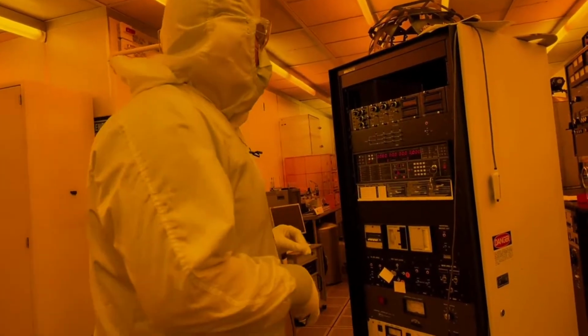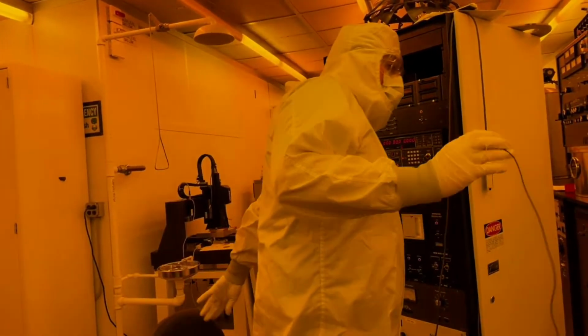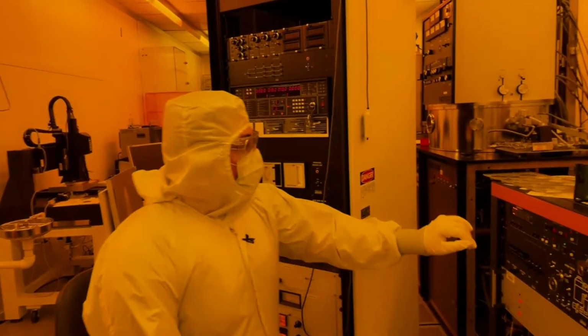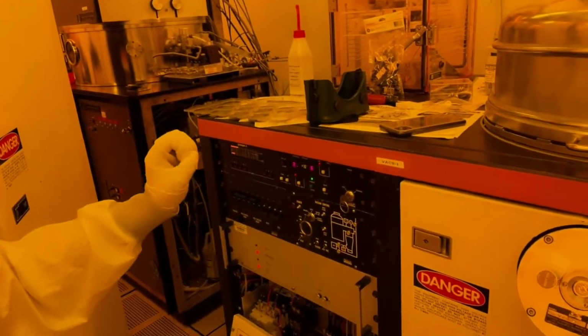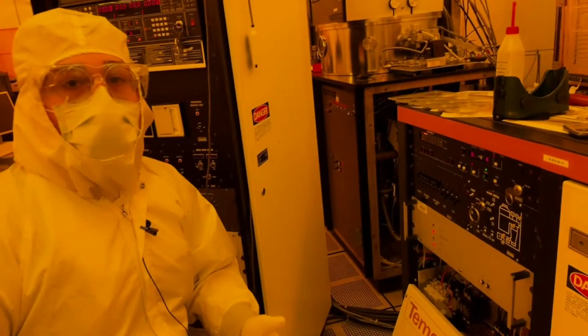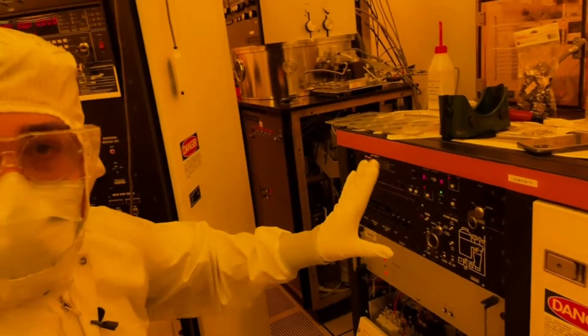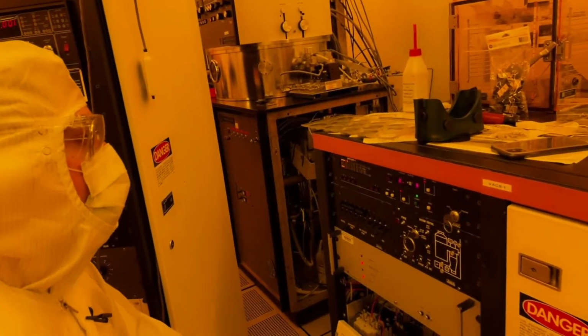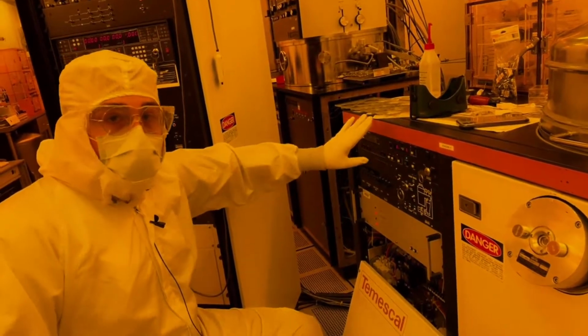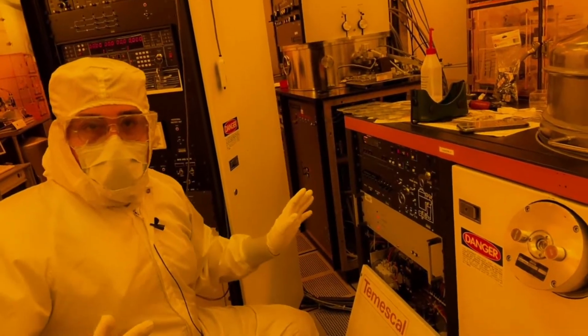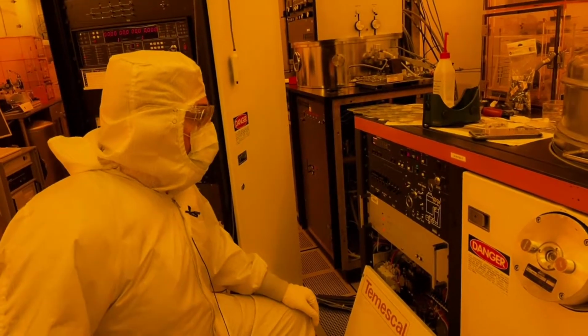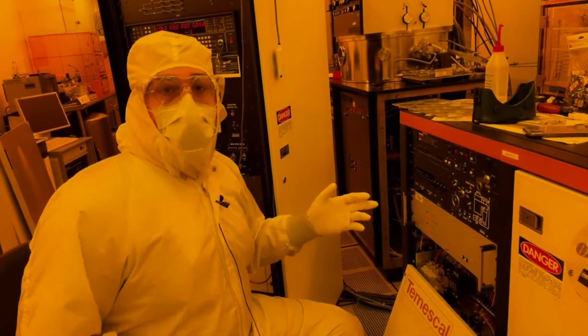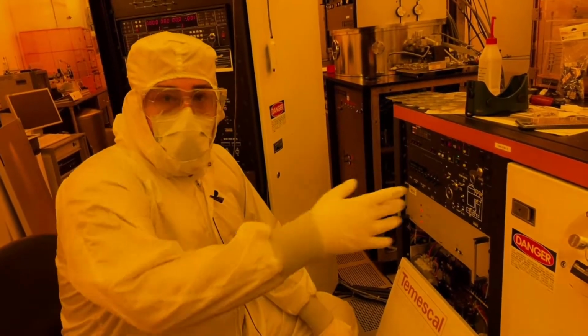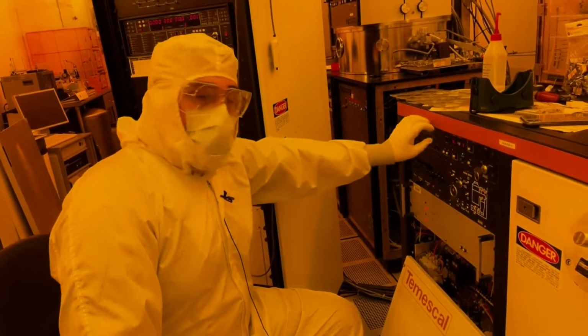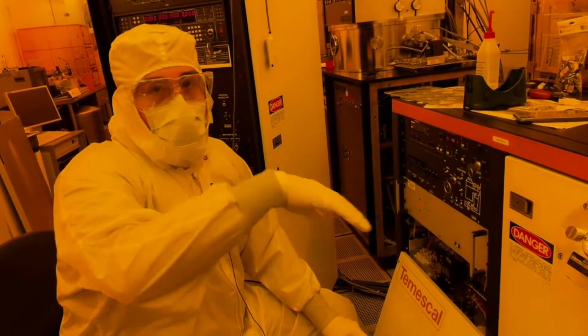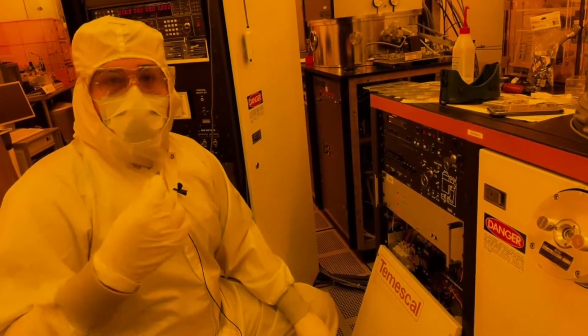The other problem that we've had with this is with the ion gauge controller. These controllers are much more likely to go down than the actual gauges. This is all old circuitry. We've had an issue in the past where this controller died and it just wasn't reading the gauge at all. What we did is we had an extra one of these. We cannibalized parts from it, put it back together, and we got it to run again. So again, it's way more likely that the circuitry is going to go out than the ion gauge. The ion gauge is a pretty simple thing, and it's basically like a light bulb too. You'll be able to see if the filament is damaged.